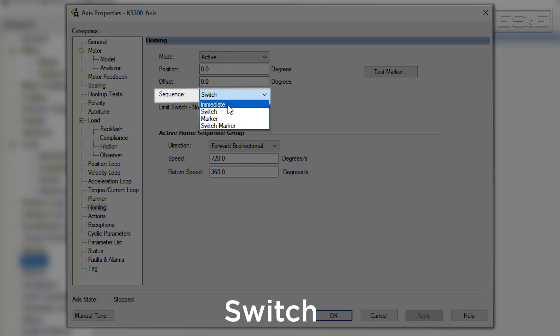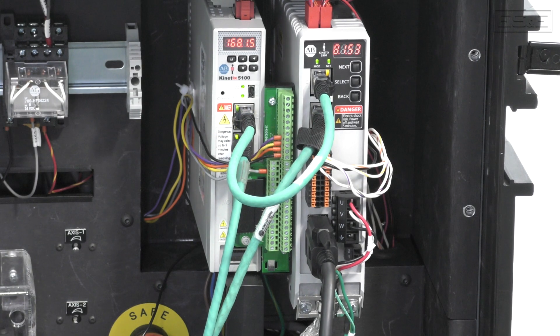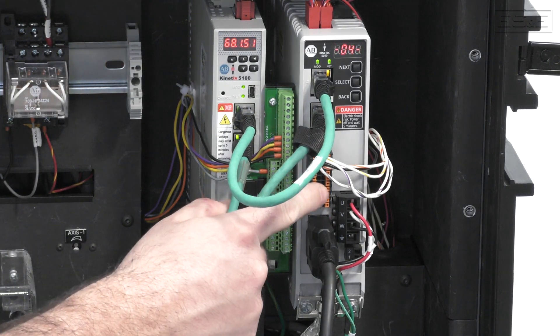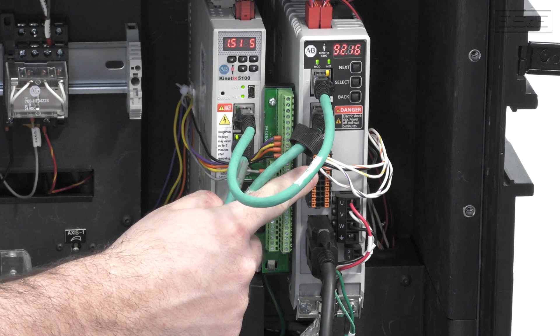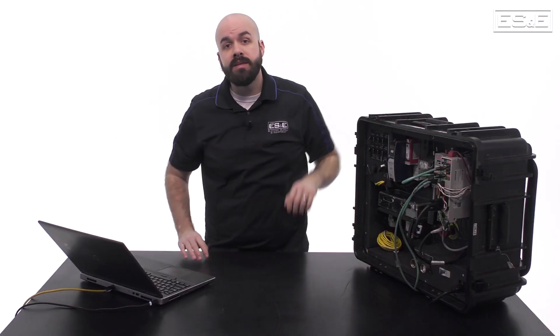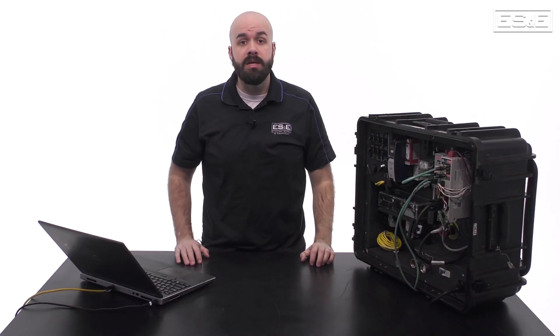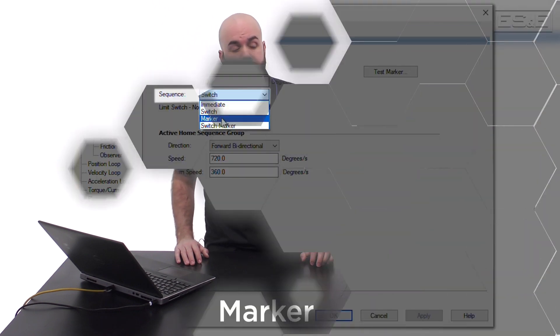If switch is selected, then the axis will need to move to the home switch before redefining the actual position. If the mode is set to active, then this will happen automatically when the MAH is executed. The home switch will need to be wired to one of the digital inputs on the front of the drive. This digital input will also need to be configured as the home switch in the module properties of the servo drive.